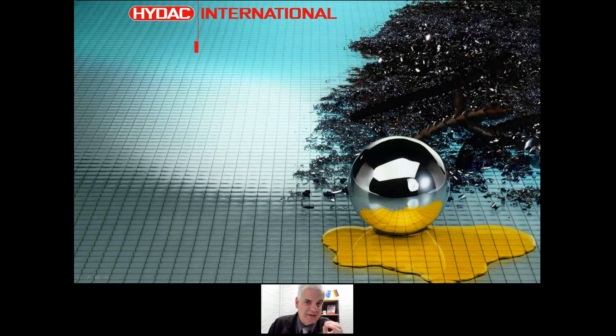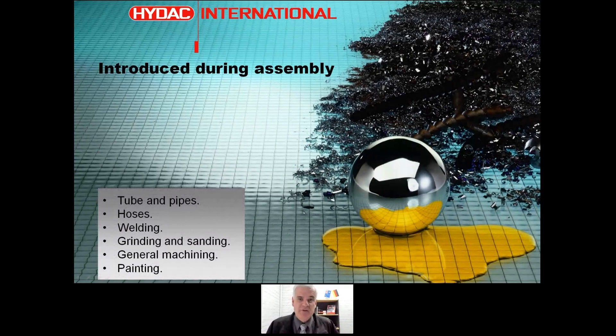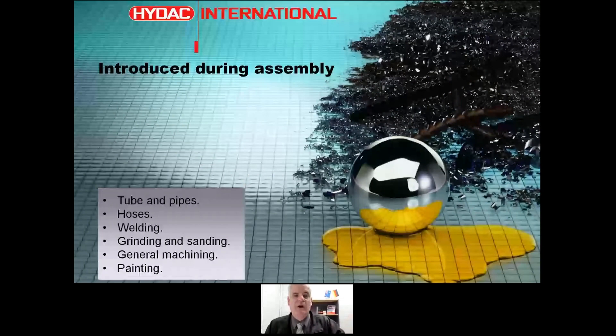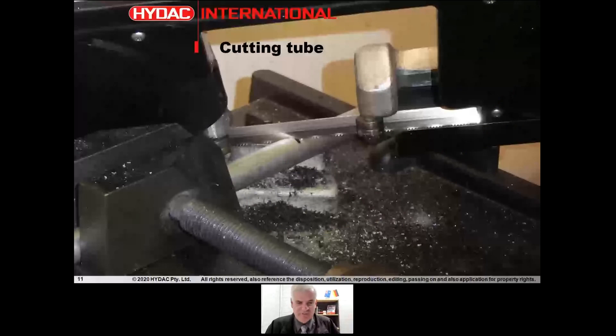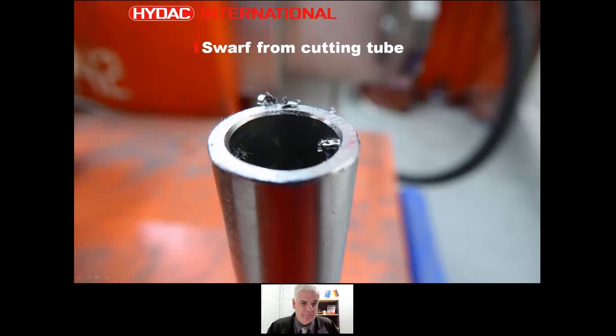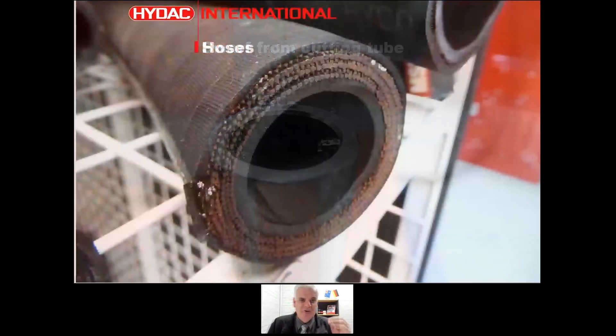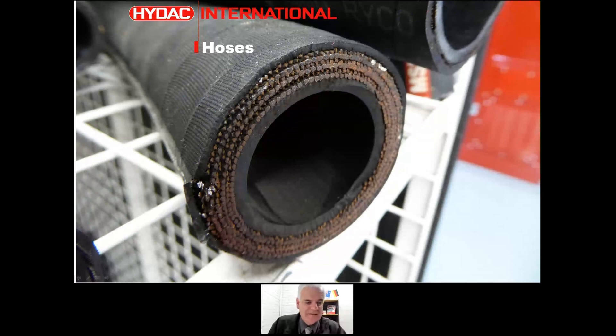A lot of contaminants in the system can be introduced during assembly through tubes and pipes, hoses, welding, grinding, sanding, general machining, and painting. We're going to be cutting tube — there's a lot of swarf involved. It's absolutely critical that these large chunks of steel are excluded from our system. The same is true with hoses. Hydraulic hoses can sometimes comprise as much steel as a similar size tube or pipe, so as we cut them there's a lot of steel released into the hose.